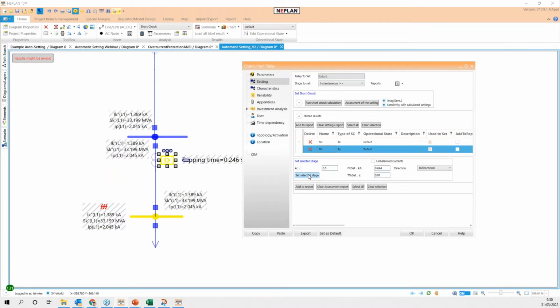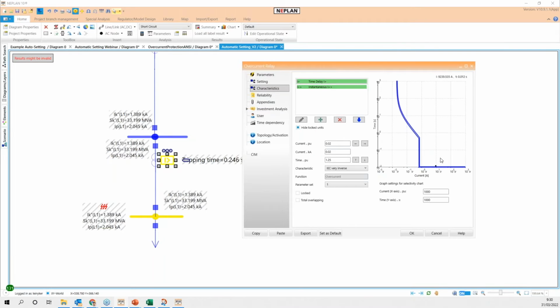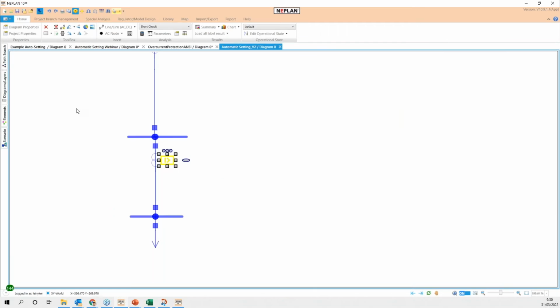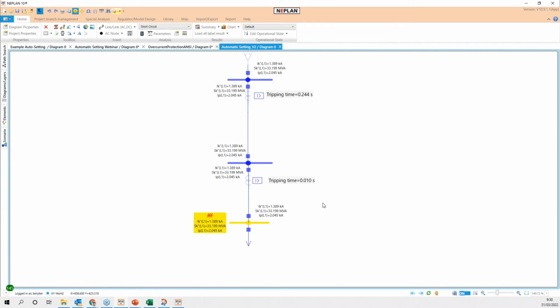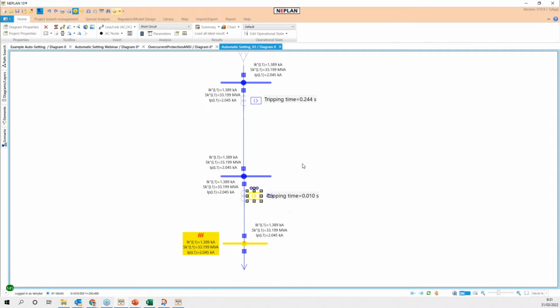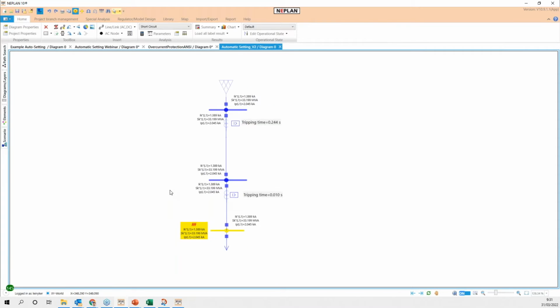We can change the setting of the protection. And if we come to the new operation, we can see that we have moved the pickup of the instantaneous unit. If we run the simulation now, we can see that for this fault location, the tripping time of this relay is now working in the instantaneous unit. And for sure, we have a very convenient difference in time between both relays. Well, as I am mentioning, this is a very, very simple example, but it has allowed me to present some characteristics for automatic setting with NEPLAN.